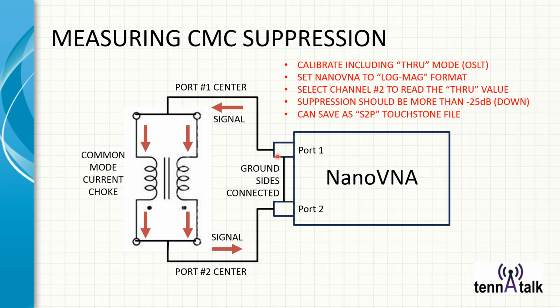Now I want you to notice we basically jumper the ground side of both ports together, and the center pin only gets connected to both leads on the input, and then the center pin of port 2 gets connected to both leads on the output. Why is that? Well, we are trying to drive current in the same direction through both sides of the CMC. And the CMC is really there to try to resist that flow of current. And you want to see how good a job it's doing resisting that flow of current at common mode. That's why it's called common mode current on both sides of the connection.